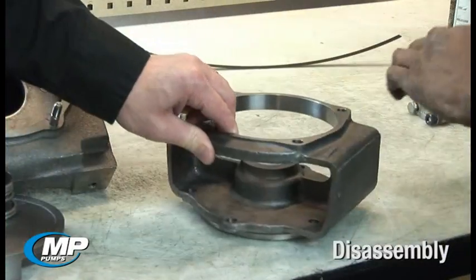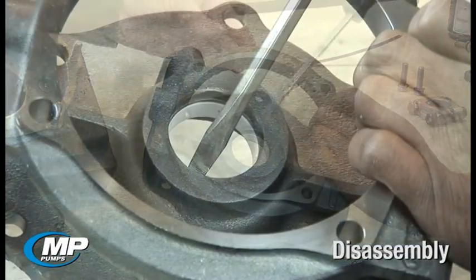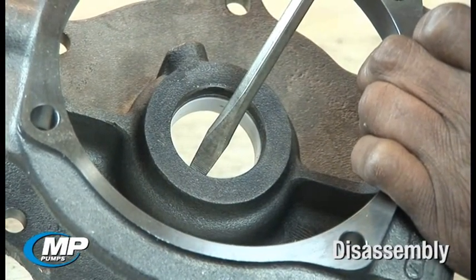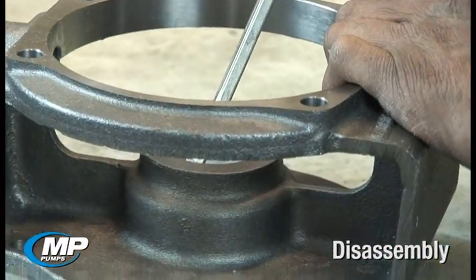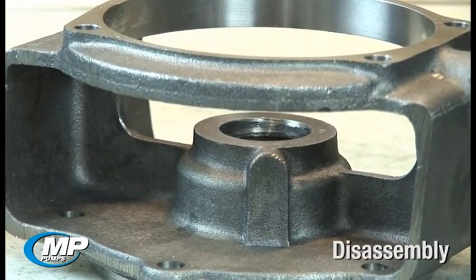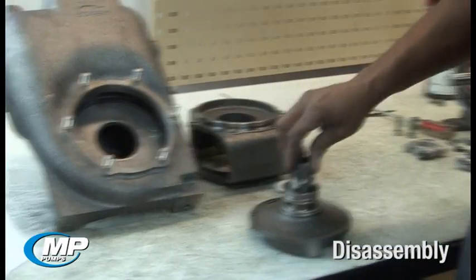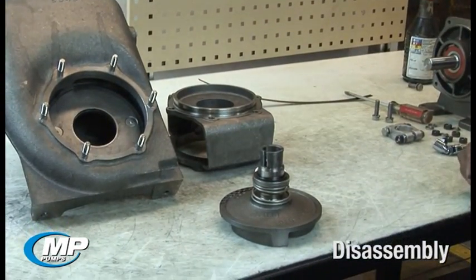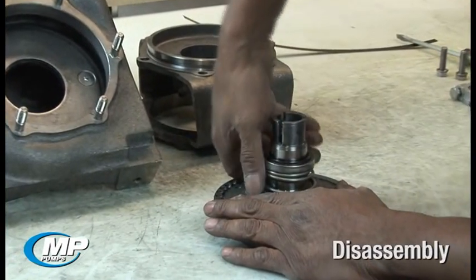The stationary seal face can now be removed from the adapter by turning the adapter over and using a piece of wood or screwdriver on the drive side of the seal face, and driving the seal face out of the adapter bore by gently tapping on the end of the tool. The rotating element can be removed from the drive sleeve by working the seal face and bellows assembly back and forth while pulling it from the drive sleeve.